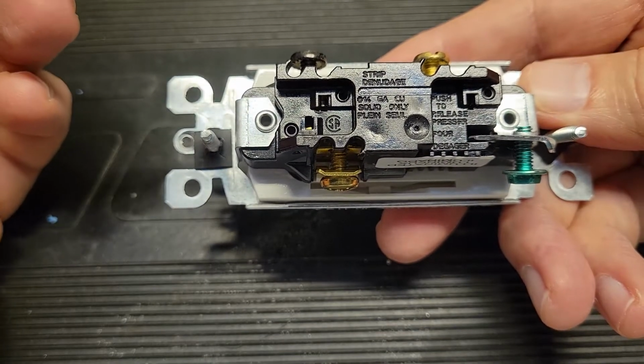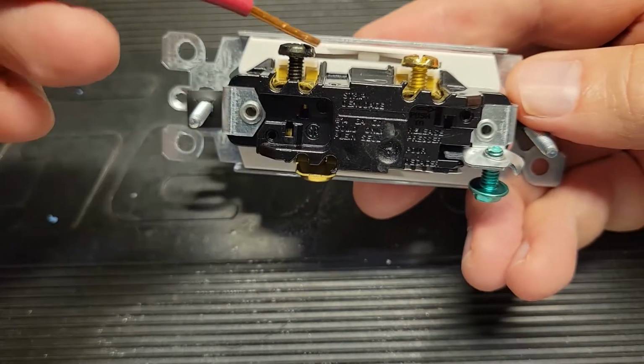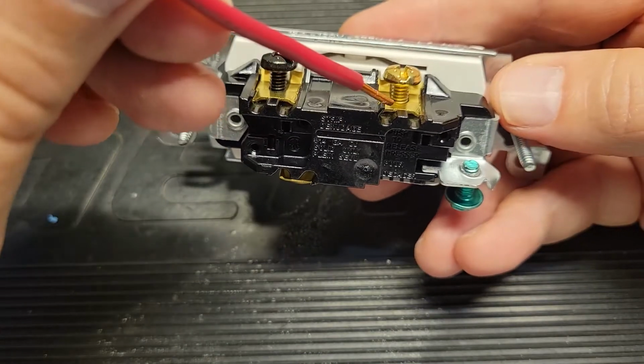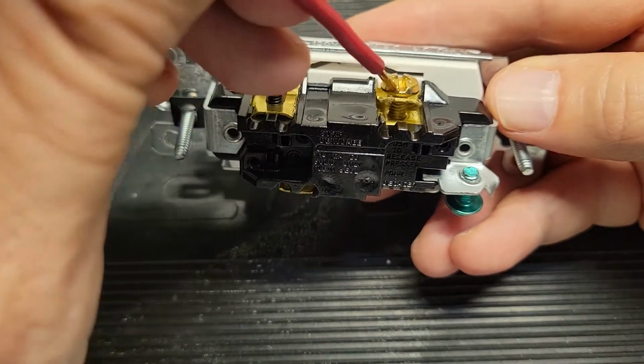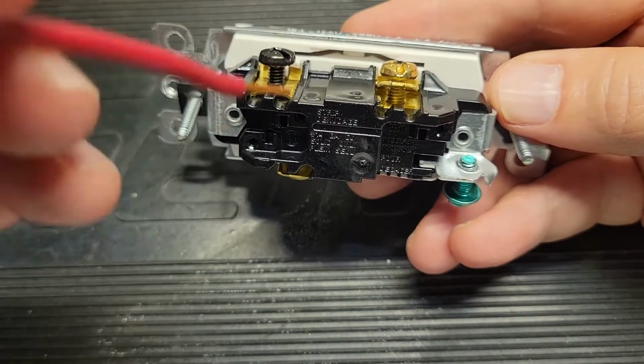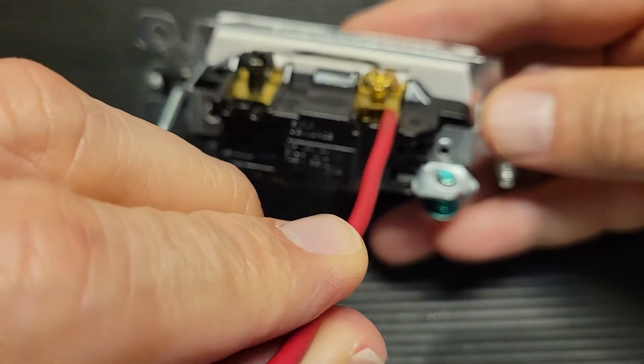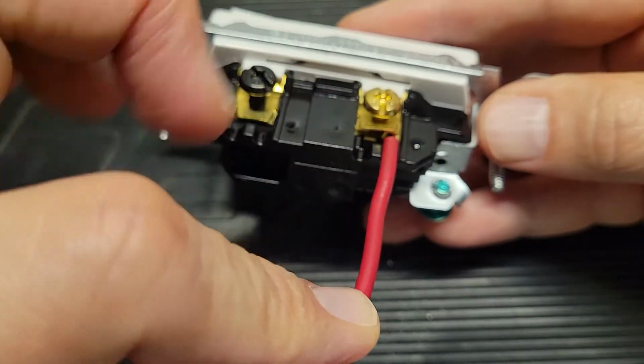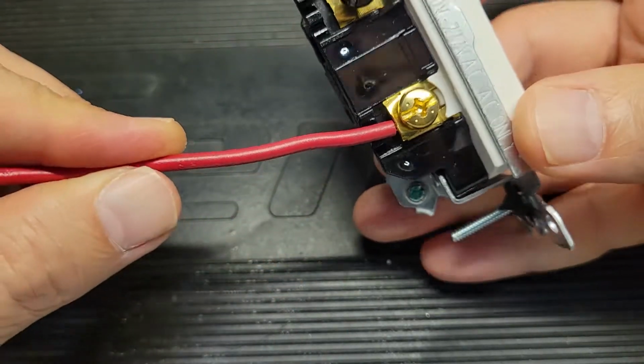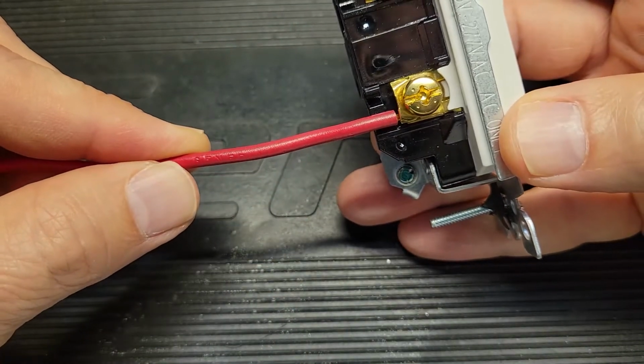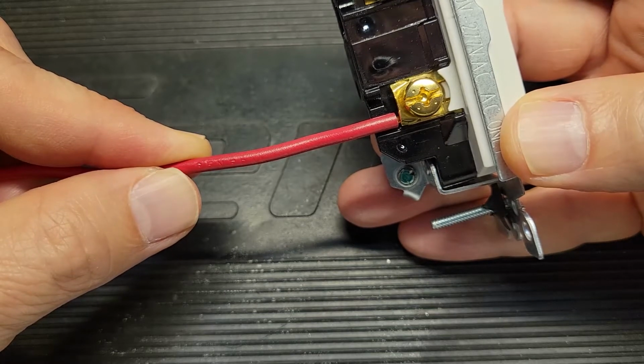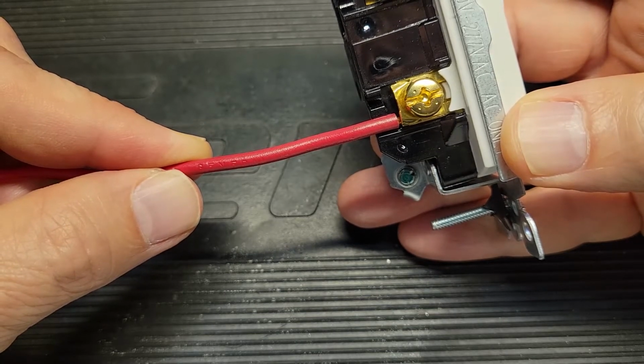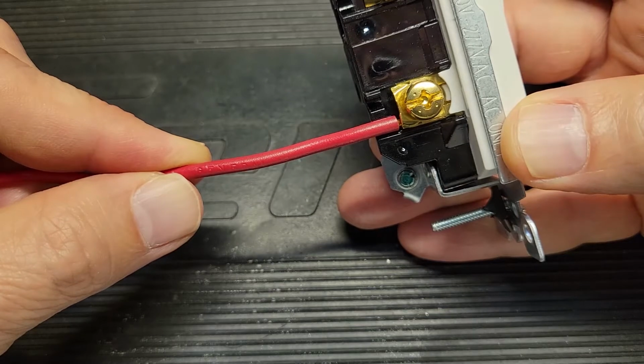Finally, the last one is called the back connection. You'll notice there's a plate here that lifts up, and if I get underneath it, I can go all the way to the bottom. Now I tighten that screw, and as you see, the insulation is just right up to that clamp—we can make a secure connection this way also.